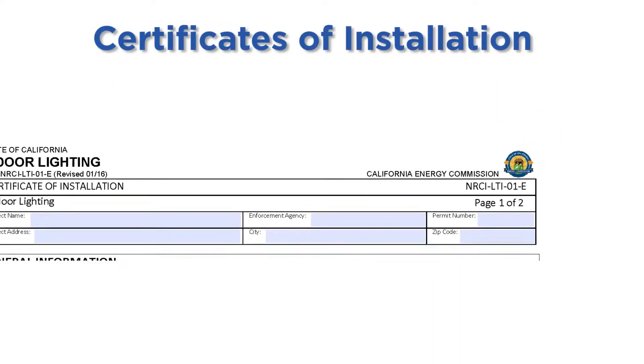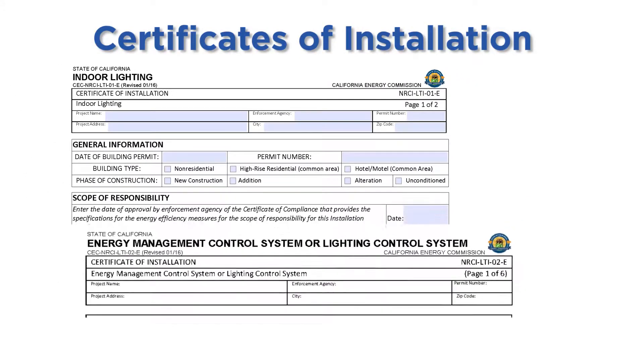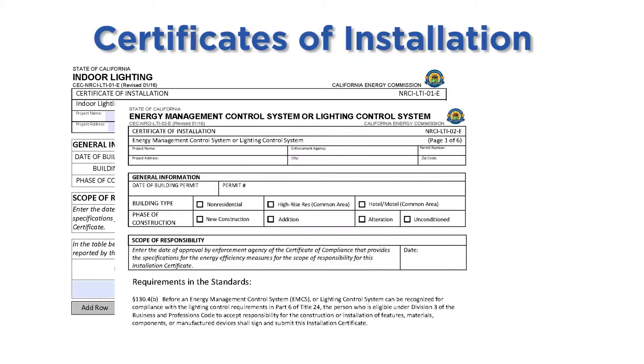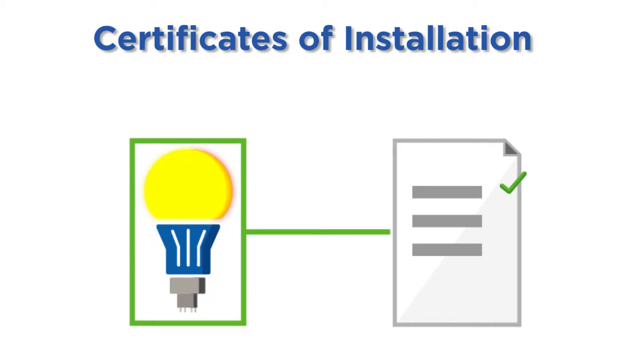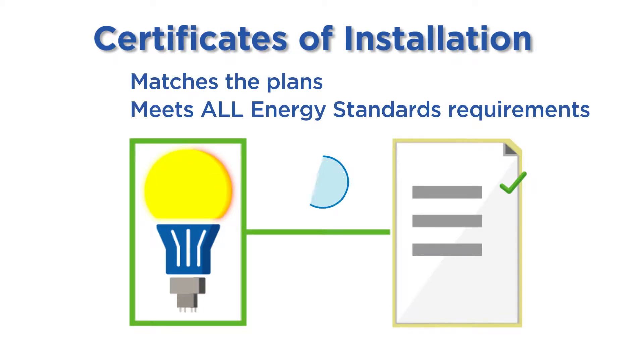The certificate of installation forms are completed during the installation phase by the installer or contractor. These forms are a declaration by the installer or contractor that the installed lighting system matches what is proposed on the plans and that controls and systems meet all energy standards requirements. The certificate of acceptance forms are completed by the acceptance test technician after the lighting system is installed, prior to final inspection. The building inspector can reference these forms to help with their inspection and to ensure that all tests have been passed and that the lighting system is operating to code.